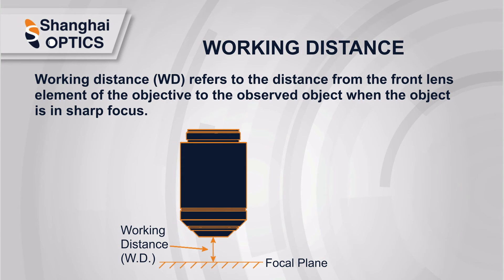Usually, the working distance refers to the distance from the front lens element of the objective to the observed object when the object is in sharp focus. Objective lenses with a long working distance are needed for many scientific research applications, such as atom trapping and analyzing fluid samples that require putting an object in a chamber. The resolution of a microscopy system can be significantly affected if the observed object is not placed on the design object plane, especially for an objective with high numerical aperture.